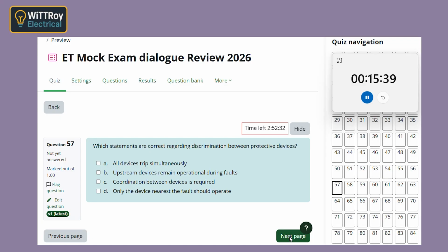Exactly. Question 57. Discrimination between protective devices. I remember this one a bit. Only the nearest device should trip? Yes, that's the main goal. Let's say there is a fault on one branch circuit. Ideally, only the device protecting that branch should trip, and the rest of the installation should stay energized. So the upstream device stays on. Yes, if proper coordination exists.